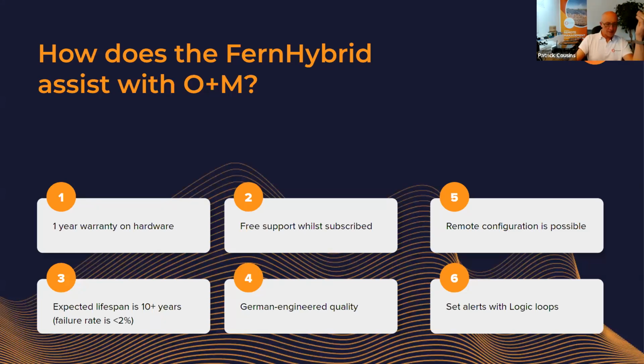Maybe I'd like to add a little to that. What's really important is that, of course, you don't want to get any failure events with these systems that are running. So you can set threshold notification triggers, as we call them. That sounds like a mouthful, but what you're really saying is, if this temperature on some sensor goes too high, or if this voltage somewhere else goes too low, send me an email or a Slack message, and then I'll at least be able to go into the entire system and have a look remotely at what could be going on. Maybe then I could immediately change a parameter to avoid a failure event. So that's one part of it.